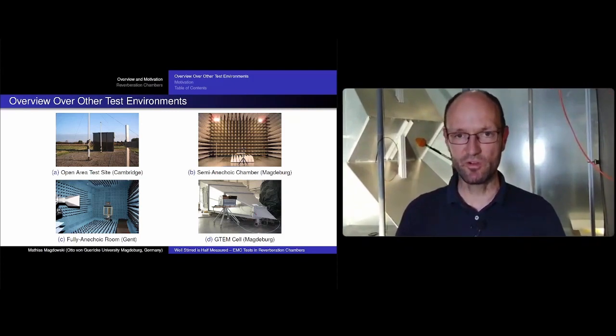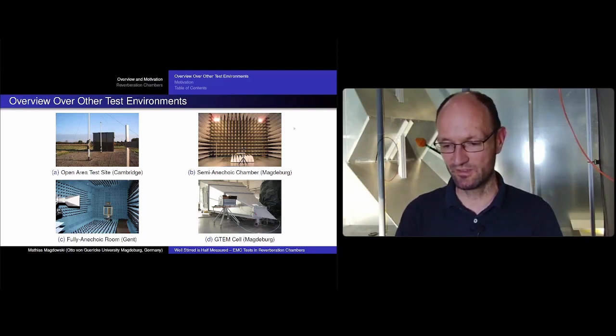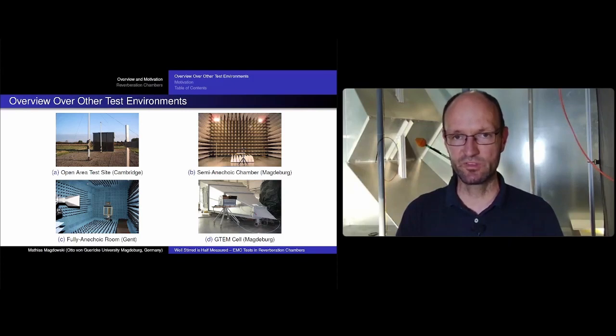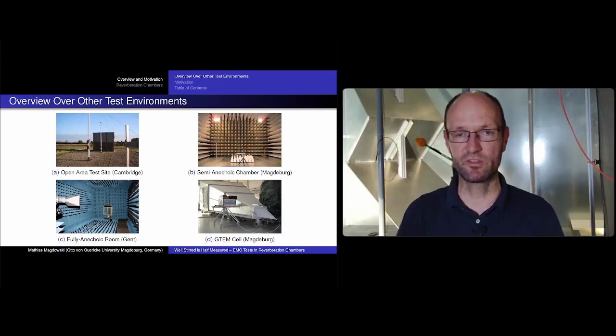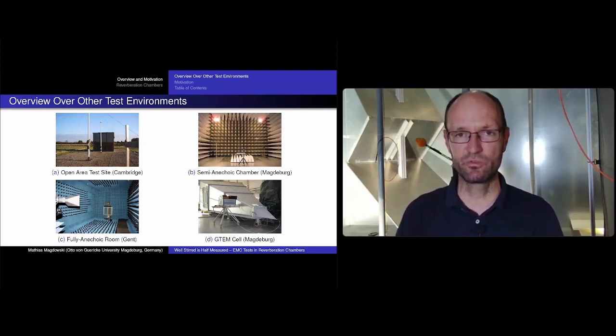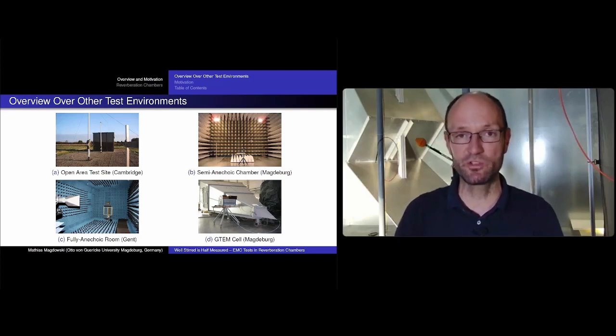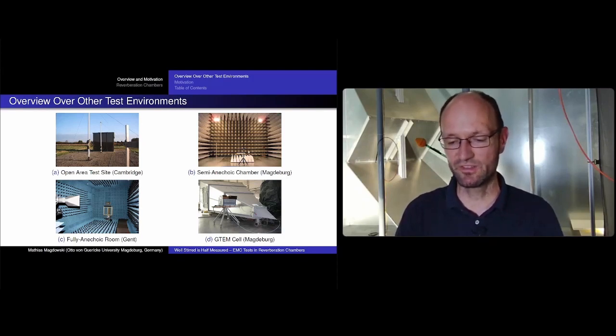Of course, you might have issues with weather in winter and so on. You can nicely replicate this in a semi-anechoic chamber. We have one in Magdeburg with a 10-meter measurement distance, so we can do measurements starting from 30 MHz. This is more or less the same as an open area test site but inside a laboratory. You have absorbers on the walls so there are no reflections, with metal behind them as a Faraday cage to shield from the surroundings — so you only measure emissions from your own device under test, and during immunity testing you only disturb the device under test and not half the city.